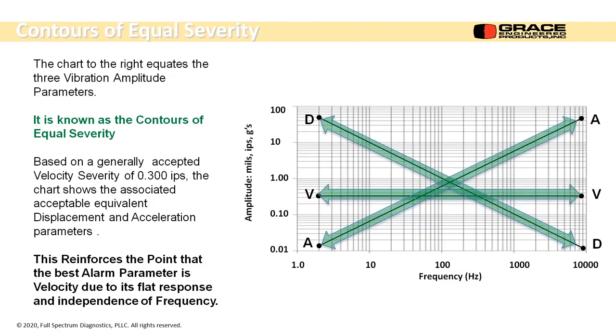Here's what's called the contour of equal severity. This is the velocity measurement. So I have it from 2 hertz up to 10,000 hertz. It's pretty flat all the way across there. These are the equivalent displacement for this value of vibration. So if this is 0.3 inches per second at 10 hertz, the equivalent displacement limit is 10 mils. Okay. The equivalent acceleration limit at that 10 hertz is 0.07 Gs. So 0.07 Gs doesn't mean anything to me. 10 mils doesn't mean anything to me unless I know for sure what the frequency is. It's so much easier just to use the velocity as an across the board severity limit. Okay, so reinforcing the point, the best alarm parameter is velocity due to its flat response and its independence of frequency.